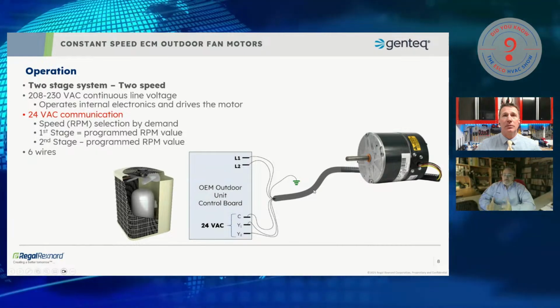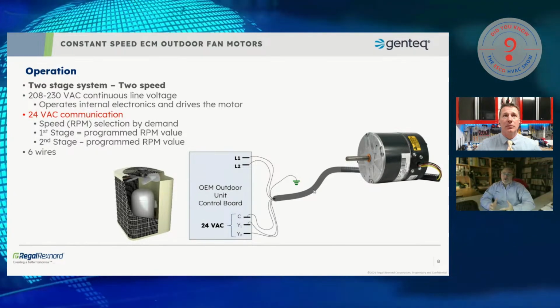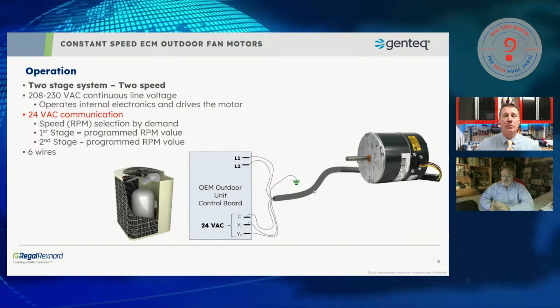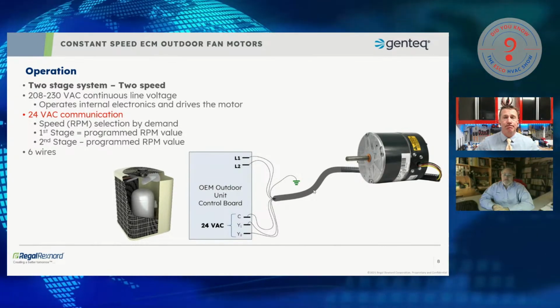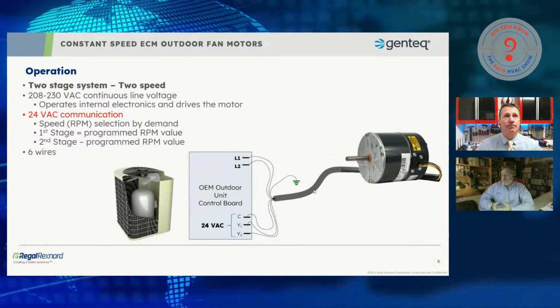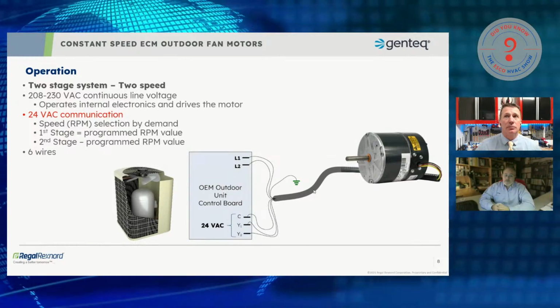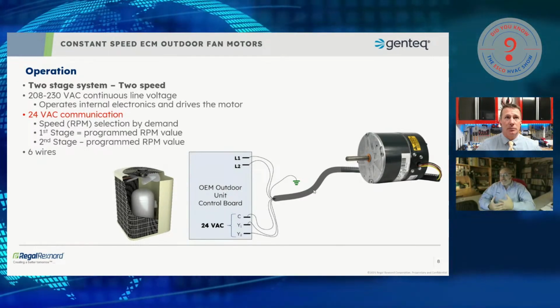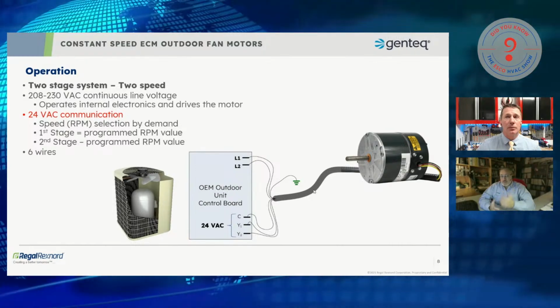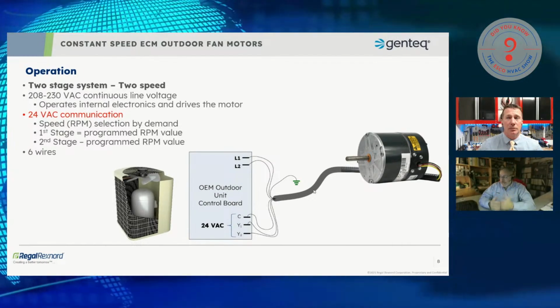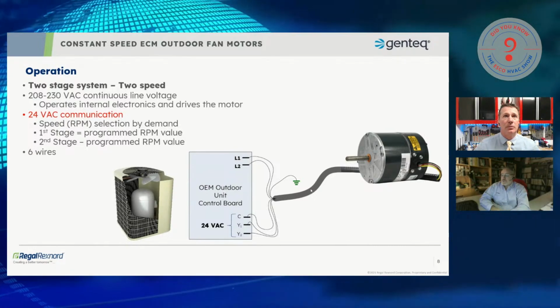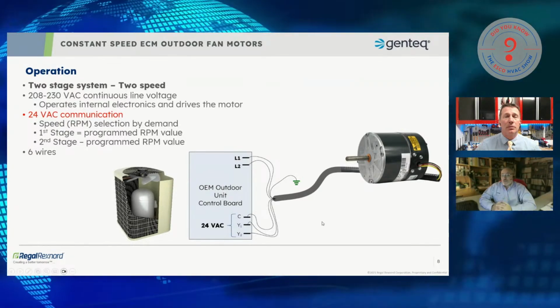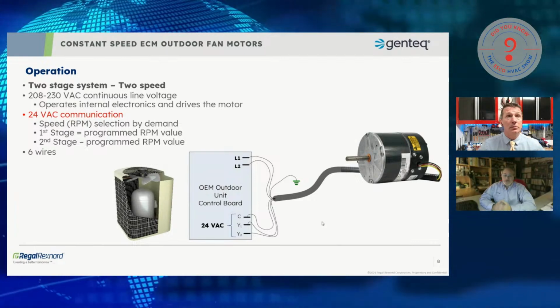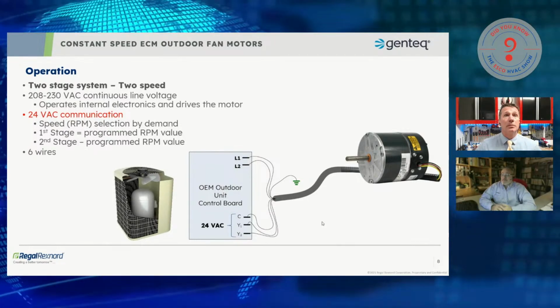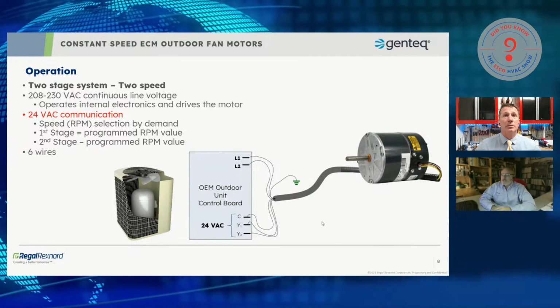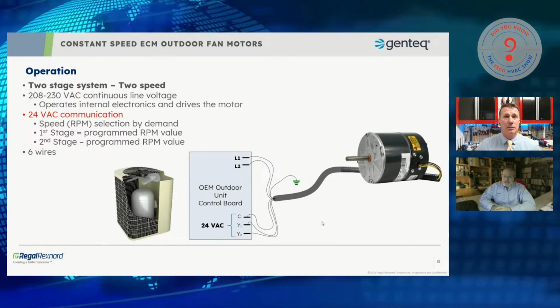Okay, so let's start out with one of the first and most common types of uses of this motor, and that's the two-stage unit, because again, we said these are predominantly found in your 16-plus SEER systems. In your 16-plus SEER systems, you quite often start to see two-stage be the common design. Very, very few 16-plus SEER systems are single-stage, at least to my knowledge. And the most common usage of our motor in that design is what we call discrete 24-volt speed taps. So there's two speed taps, and again, they're not necessarily taps, they're wires. So I've got two speed wires, and they're activated by 24 volts AC.